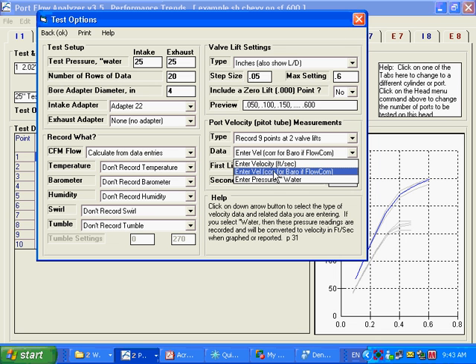Do you want to correct for the barometric pressure if you're using a FlowCom? Or do you want to enter the test pressure in inches of water? For example, if you enter it in test pressure in inches of water, you would see something like 10 or 12 inches of water pressure. But what a lot of people would rather do is convert that, let's say 10 inches of water pressure, into a velocity of maybe 120 feet per second, or if it's 140, whatever, do all the math on it.